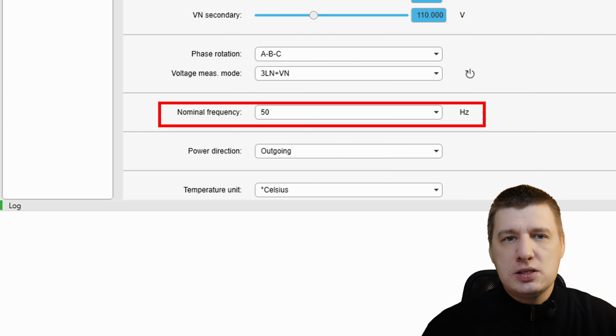Here we're discussing a setting that is often fundamental. Nominal frequency in the P5 is a single choice that dictates how the relay processes every wave of current and voltage. The nominal frequency is the rated frequency of your power system. Most of the world operates at 50 Hz, while parts of America and Asia use 60 Hz. The P5 is designed to work perfectly with either standard.